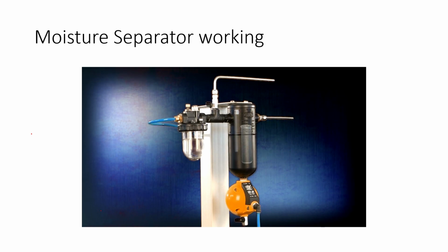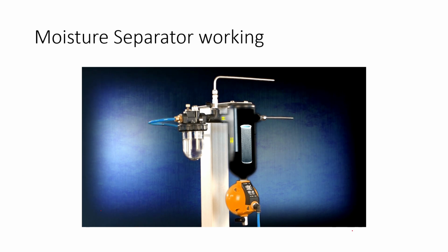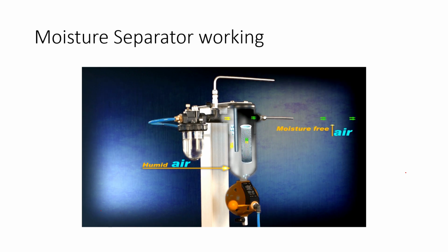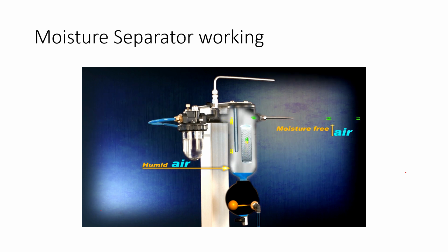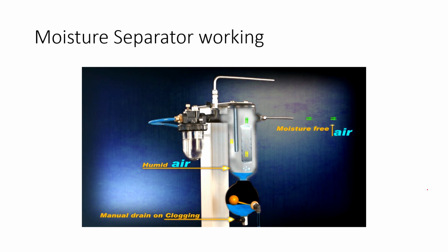Hydrant moisture separator incorporates two types of separating tools. The first of which is the baffle type. When the air strikes against the reinforced steel baffle provided within the separator on the inlet, there is a further compression at the point of strike. Any water in liquid or fog form will be initially separated at this stage itself before it has a chance to enter the inlet of the separator.